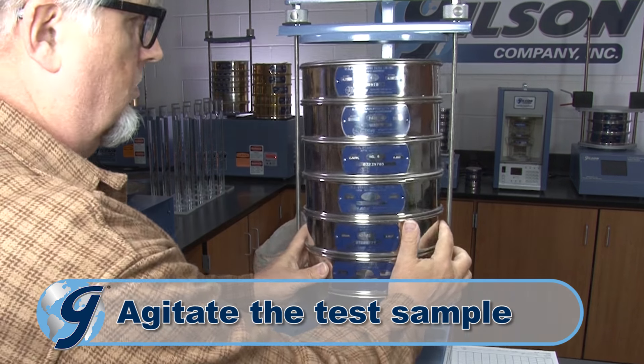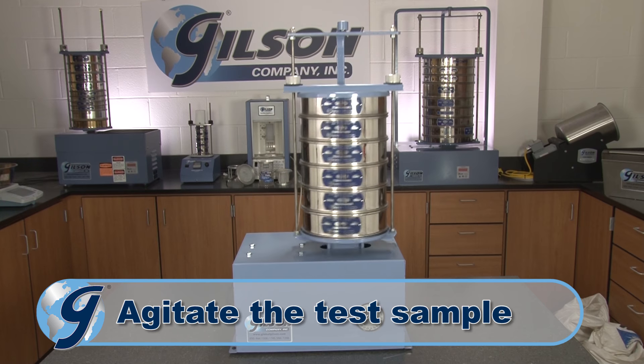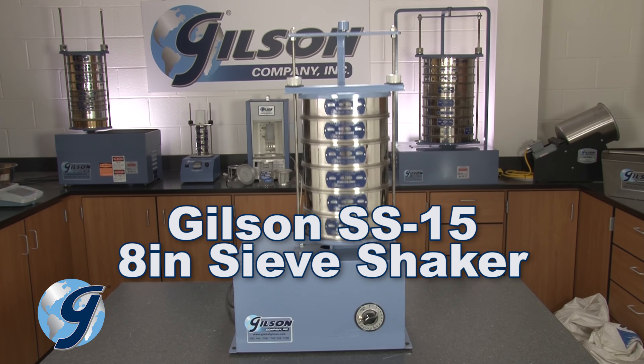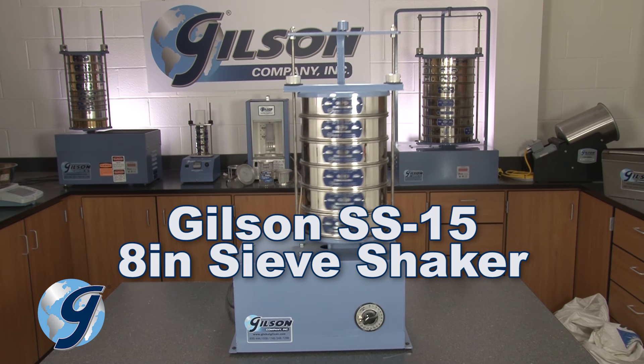Place the test sample onto the top sieve and then cap the sieve stack with a sieve cover. Agitate the sieves by means of a mechanical sieving apparatus for a sufficient period of time so that not more than 1% by mass of the material retained on any individual sieve will pass that sieve during one minute. For this demonstration, we are using the Gilson SS-15 mechanical sieve shaker, which delivers superior accuracy and repeatability for particle separations by combining a back and forth lateral motion with an up and down and tilting motion, causing test material to travel in an orbital direction on the sieve surface.